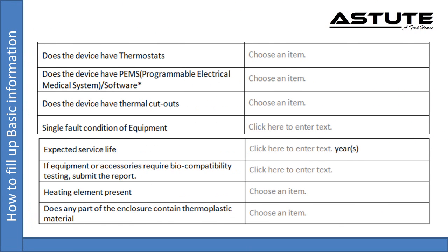Where means are provided for varying the temperature setting of thermostats in ME equipment, the temperature setting shall be clearly indicated.